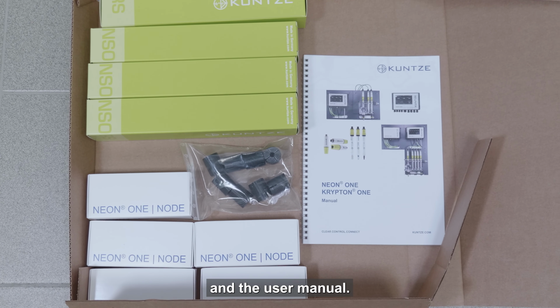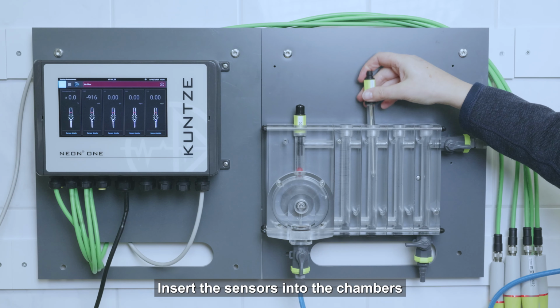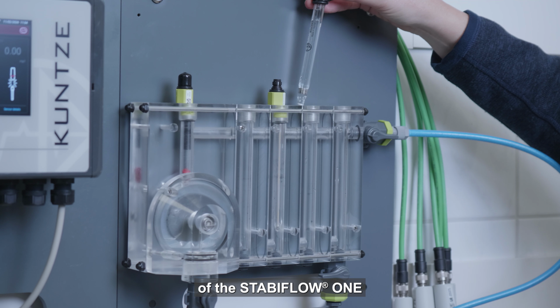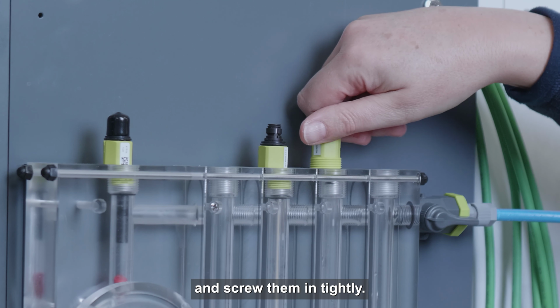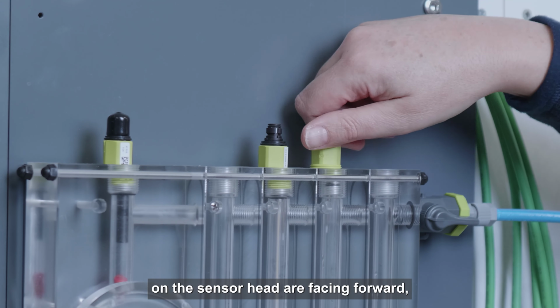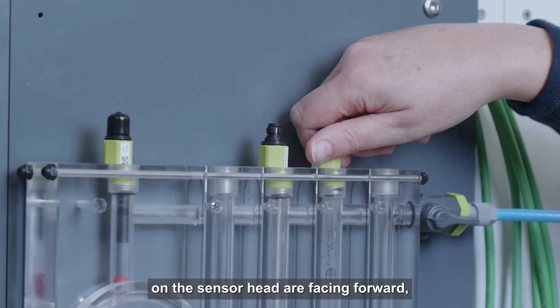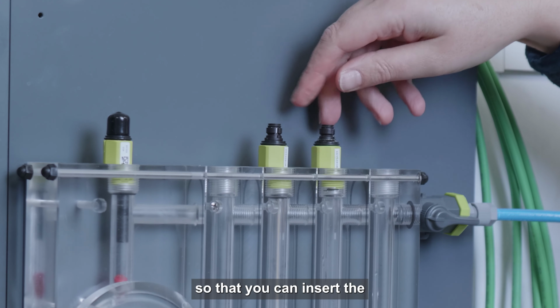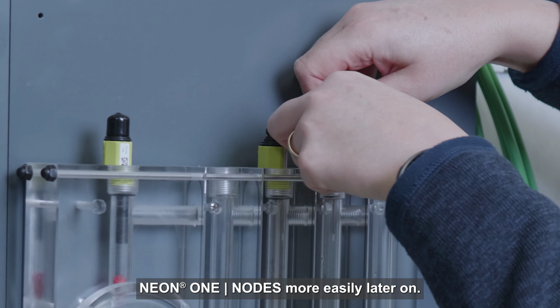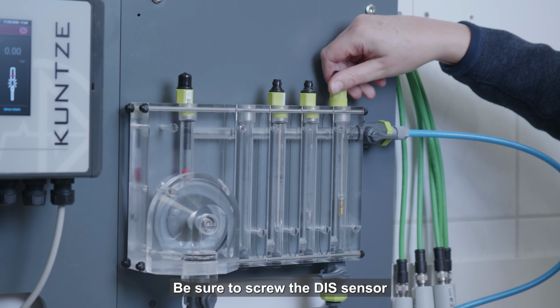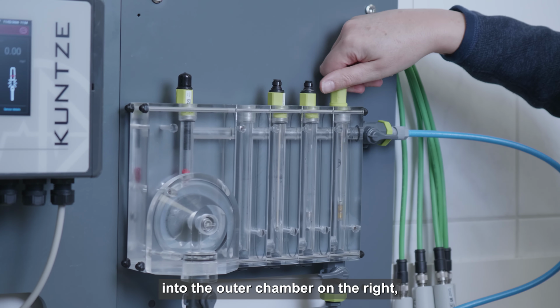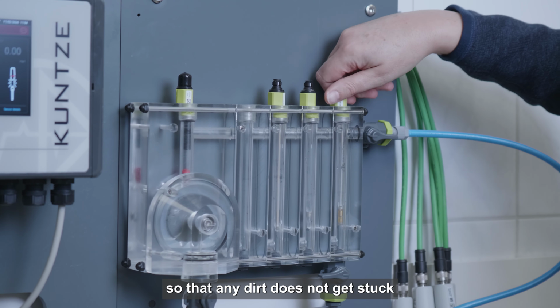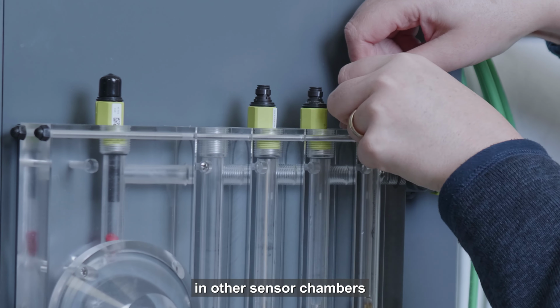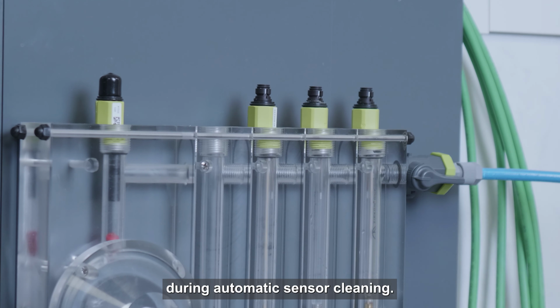Insert Zircon ONE sensors. Insert the sensors into the chambers of the StabiFlow ONE and screw them in tightly. Make sure that the white markers on the sensor head are facing forward so that you can insert the Neon ONE nodes more easily later on. Be sure to screw the DIS sensor into the outer chamber on the right so that any dirt does not get stuck in other sensor chambers during automatic sensor cleaning.